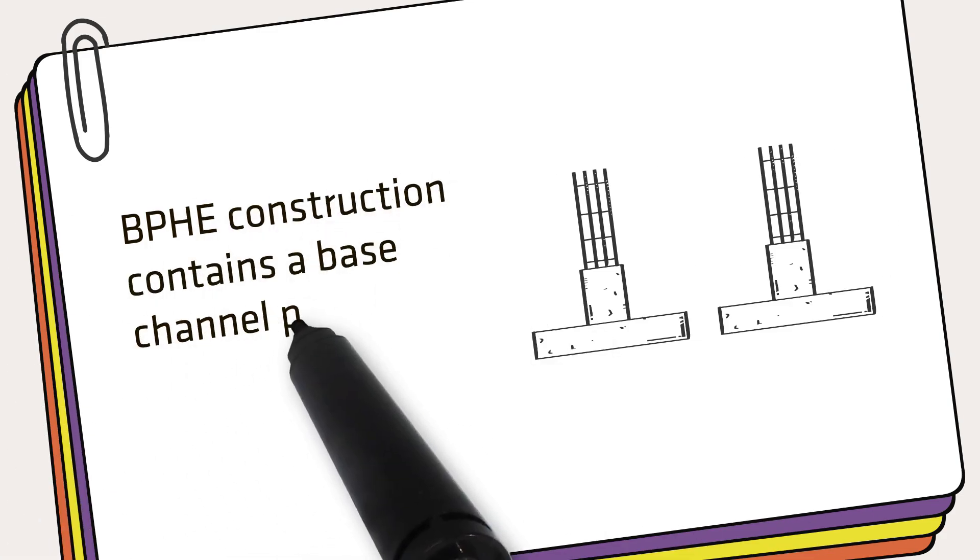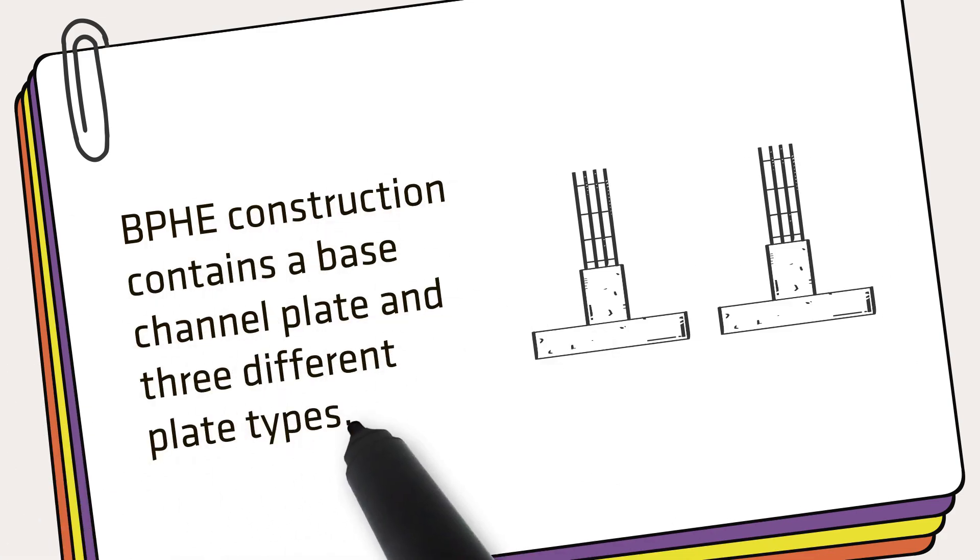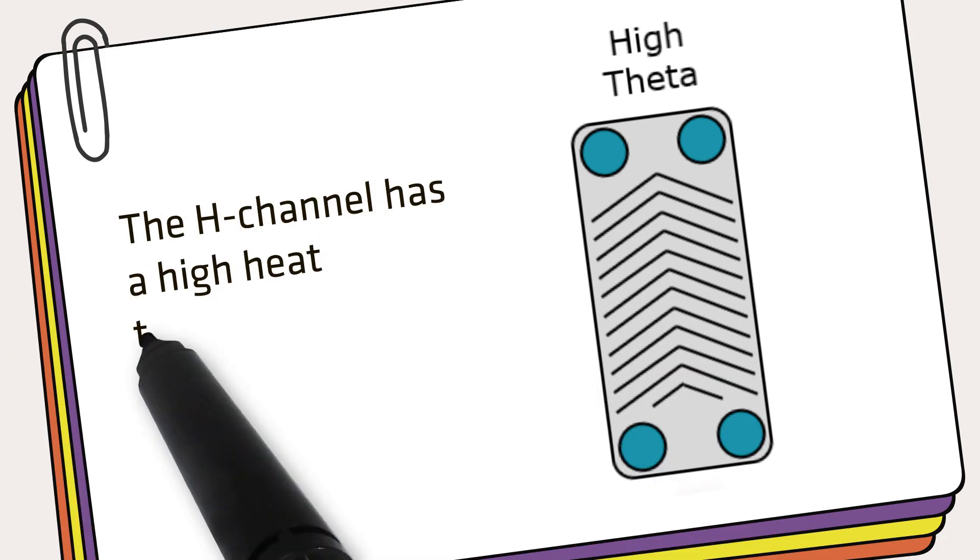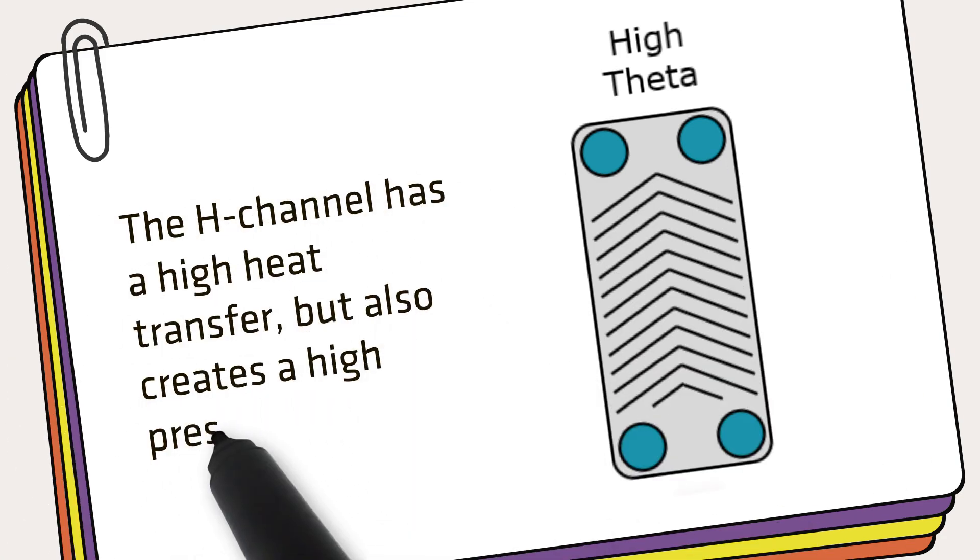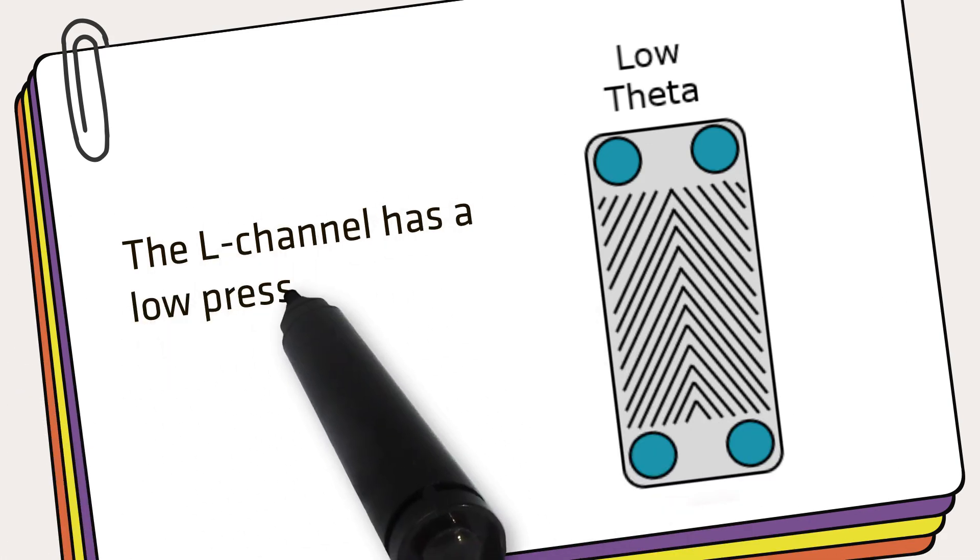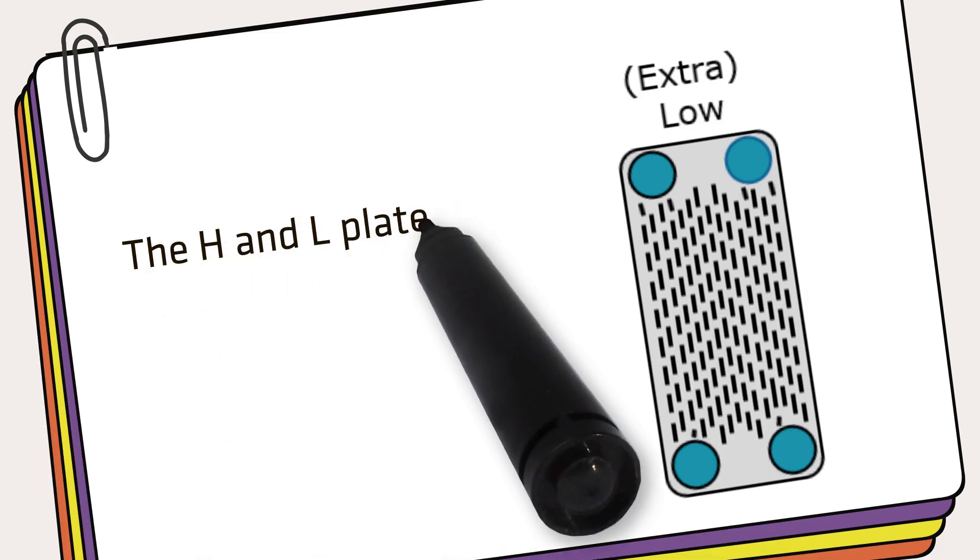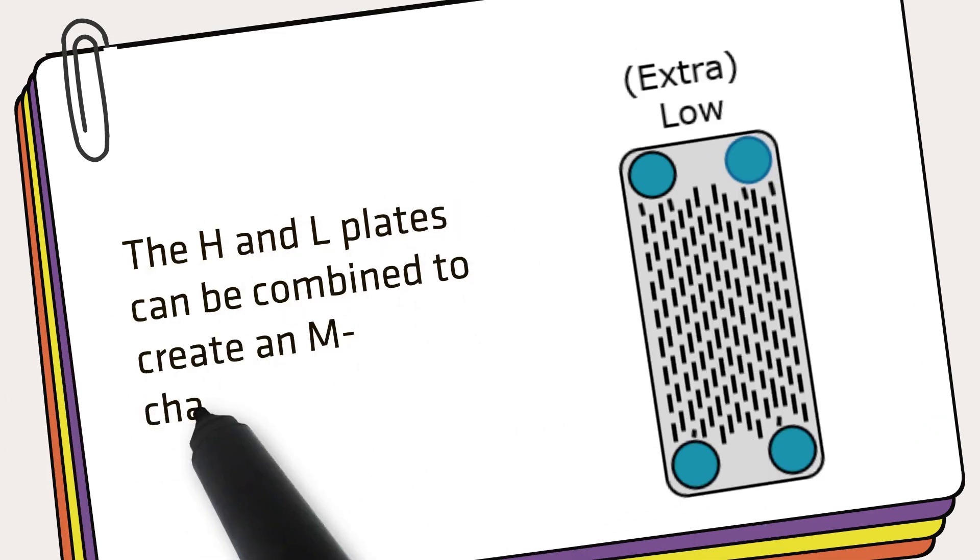BPHE construction contains a base channel plate and three different plate types. The H channel has a high heat transfer but also creates a high pressure drop. The L channel has a low pressure drop but less heat transfer. The H and L plates can be combined to create an M channel.